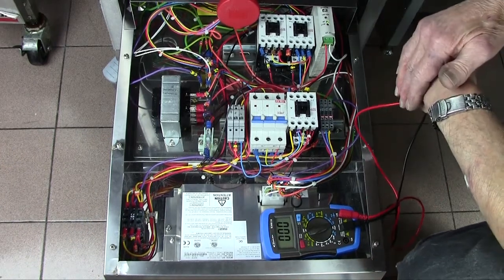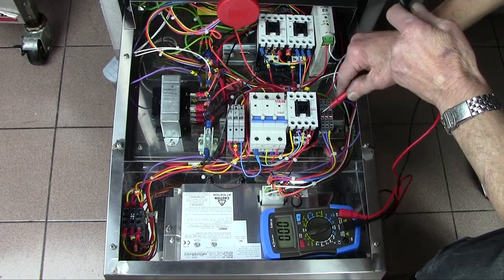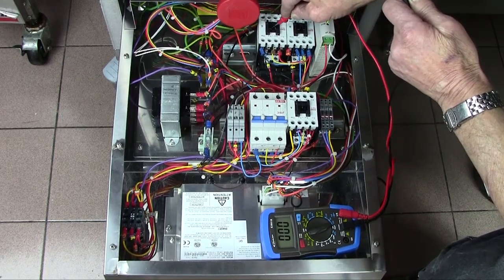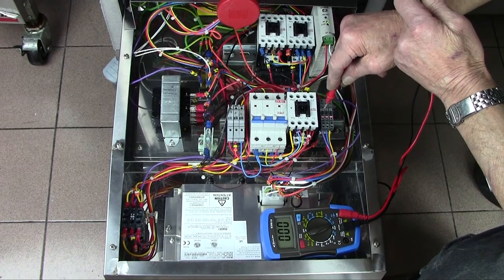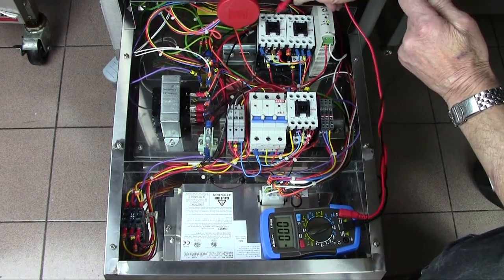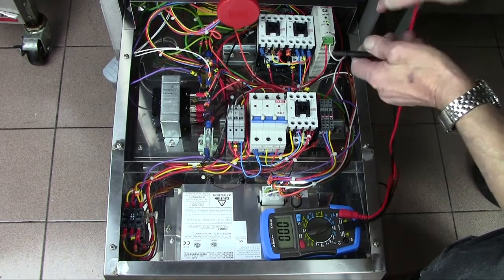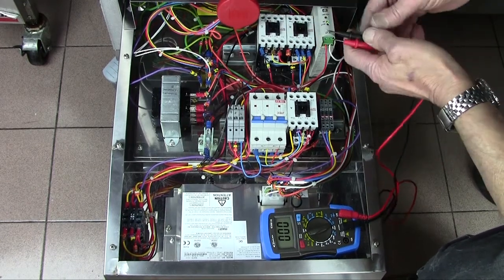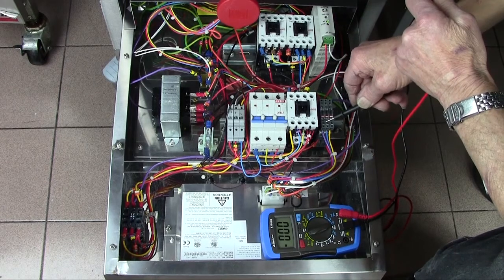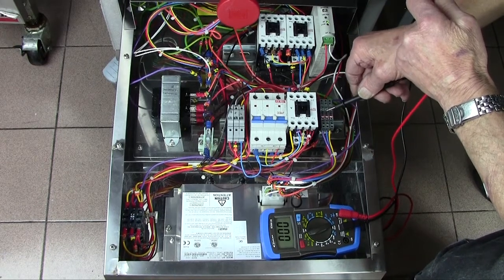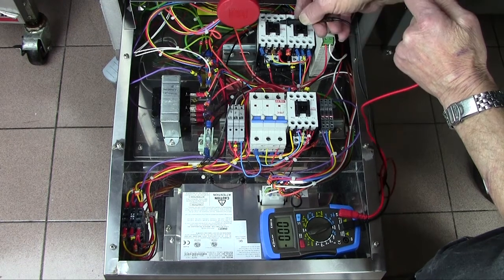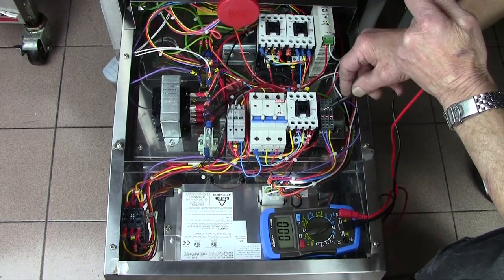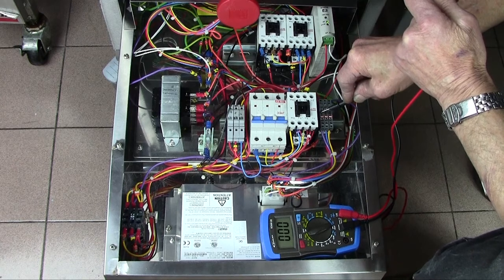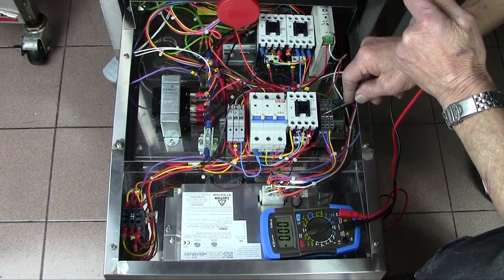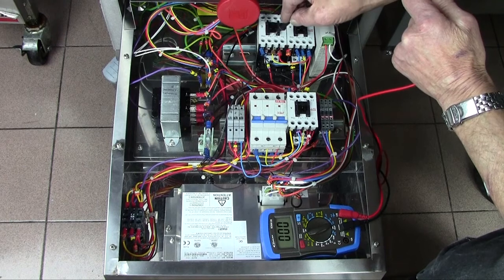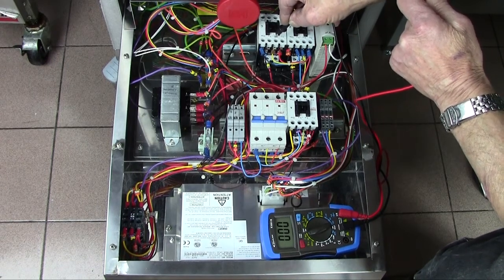You do the same checks on relay 3 and contactor C. Wait for the light to light, make sure that is in unison with that, and if it is, the coils are both good on both. If the voltage is correct at the terminals and the light is lighting and the contactor is not working, check the relay coil. If the relay coil is okay, then check the contactor coil. If faulty, replace either.